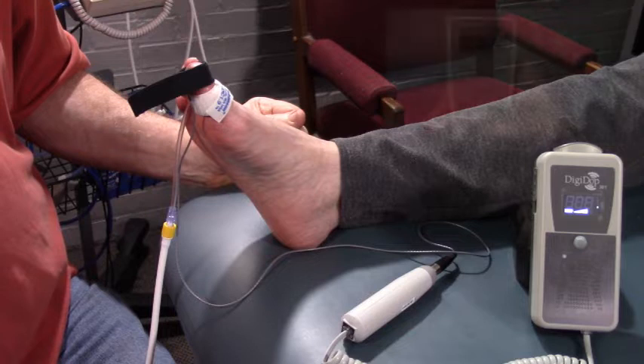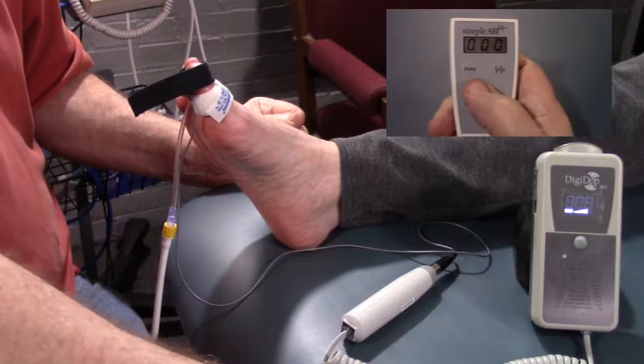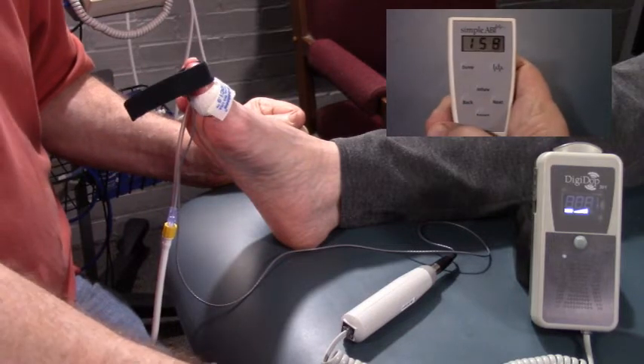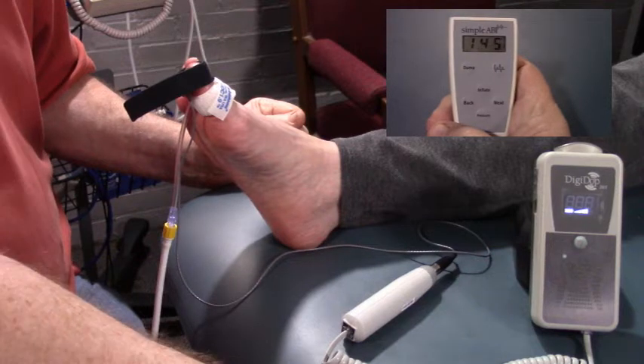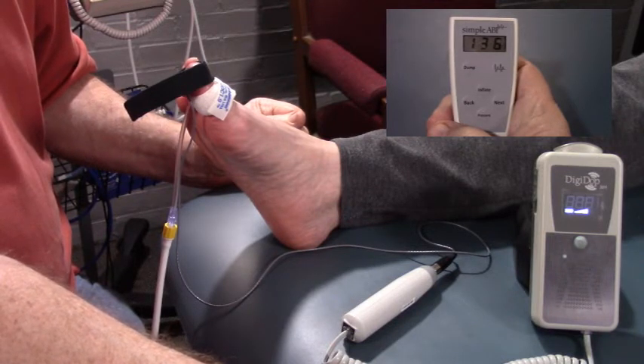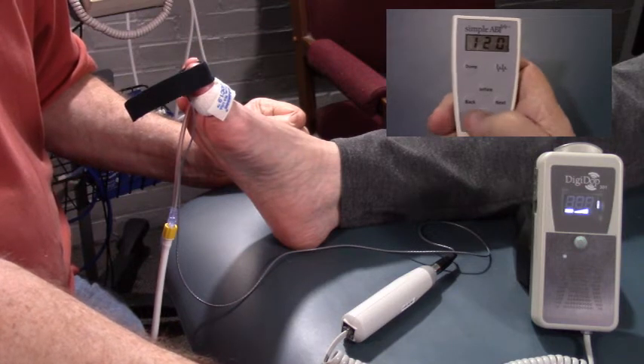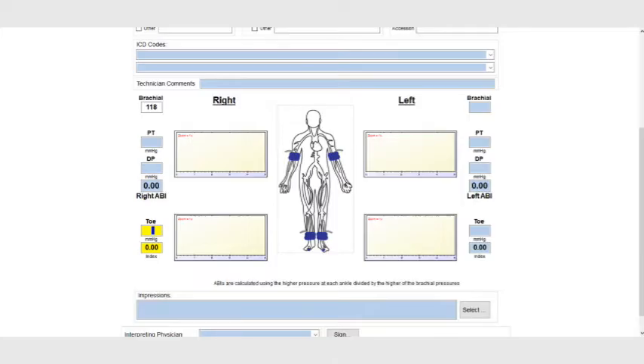It takes very little air to inflate the toe cuff, so inflate with the controller using short bursts with the inflate button. When occlusion occurs, the beeping sounds will cease, and the cuff will begin to deflate at 2 millimeters per second. Allow the air to bleed off. When the audible pulses return, press pressure to document the reading.